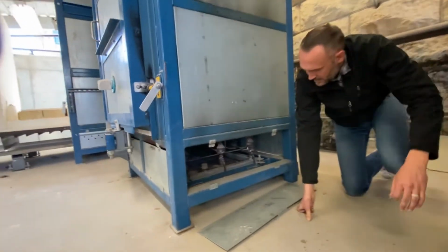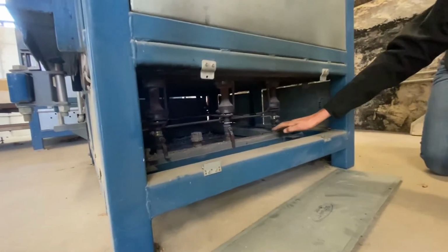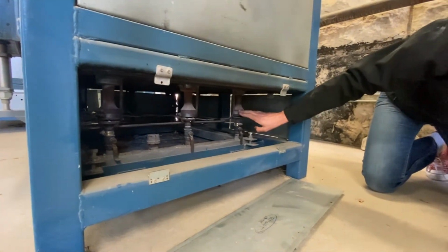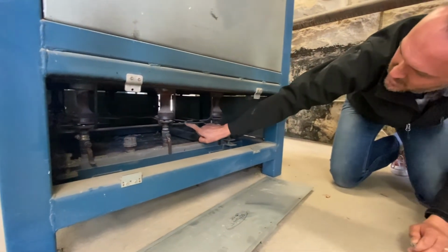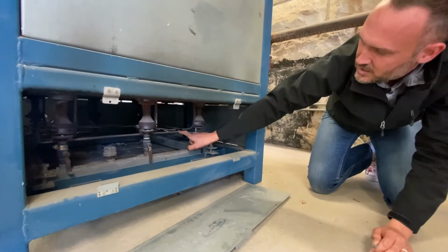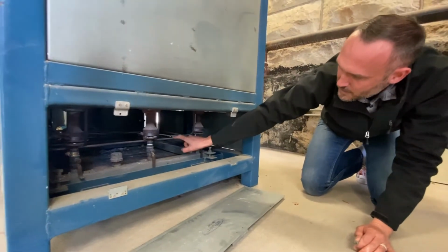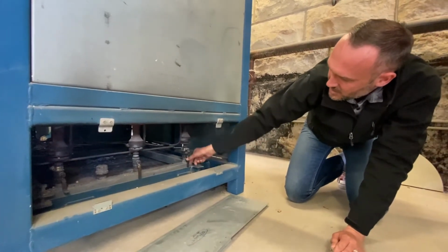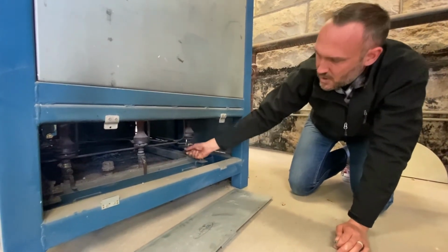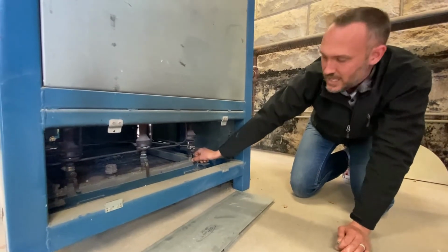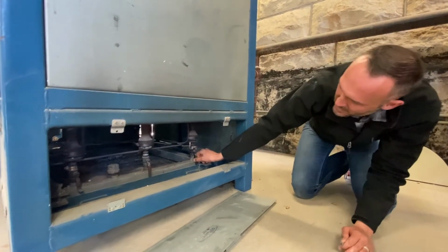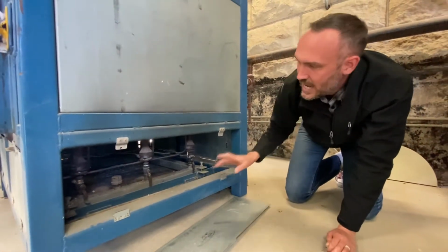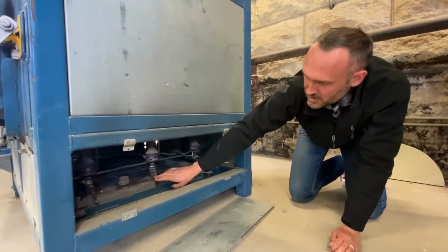Camera, if you want to come in, you can see our burner manifold. The gas is flowing through here, and we see our venturi burners right here. What we can see right here is called our pilot ring, and I'll talk to you about how beneficial that is in early stages of firing. We can also see down here on-off valves that turn each burner on or off individually. Before firing, it's important to take a peek down here, make sure there's no leaves or debris that could catch fire, and make sure that all the burners are on.